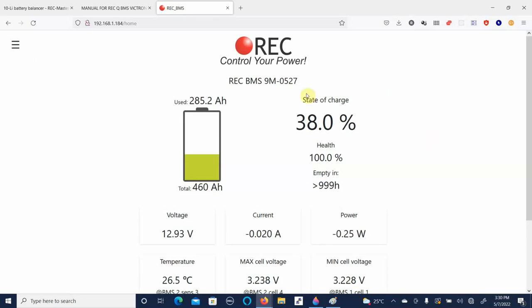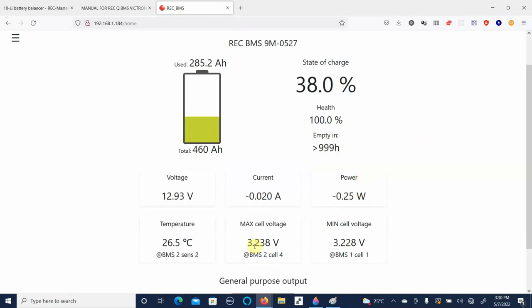So our state of charge is 38%. We're not drawing any current, so we have infinite hours of available time left. We can see that our highest temperature here is on BMS 2, sensor number 2 and 3, toggling back and forth. We can see that our highest voltage here is BMS number 2, cell number 4, and our minimum voltage is at BMS number 1, cell number 1.